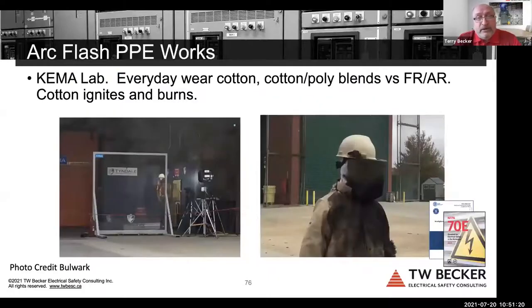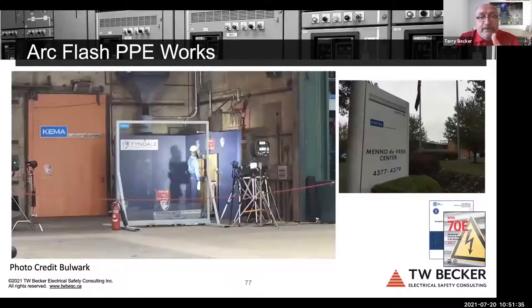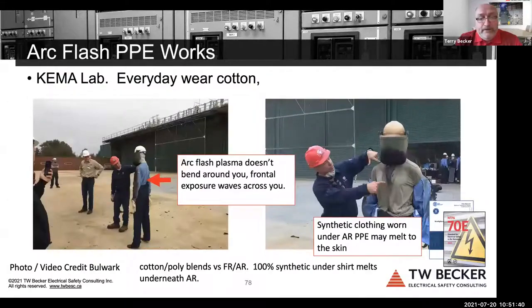Arc Flash PPE works. I've had the luxury of going to both Kinectrics and KEMA, and I'm looking at the clock. We're running down on time, so I'm going to sort of accelerate here and then open up for a few Q&As. So again, Arc Flash PPE works. Again, I've had the luxury, like I said, to see some videos of Arc Flash PPE, and I'm going to defer and probably come back to this in a separate webinar. And then in this case, that's Scott Margano with Tyndale pointing to a polyester shirt that was worn underneath and it melts. So it's important that workers have non-meltable fabric underwear, shirts, and underneath arc-rated clothing.